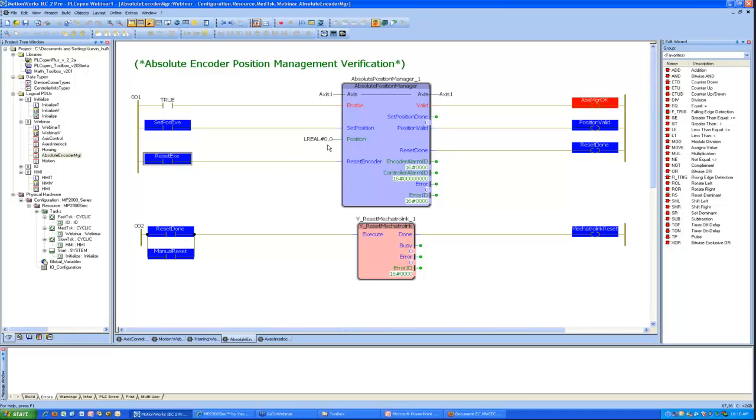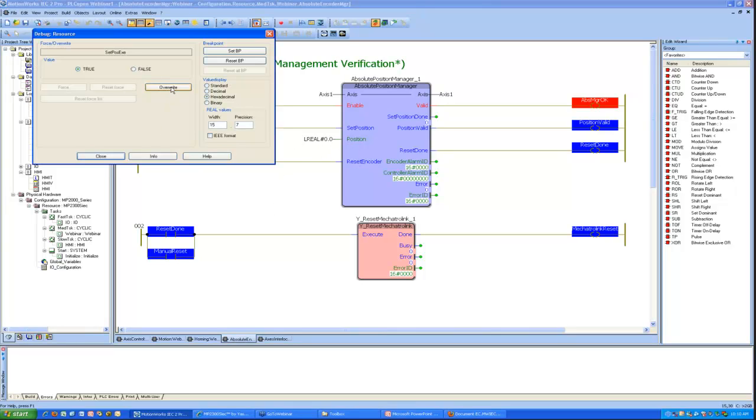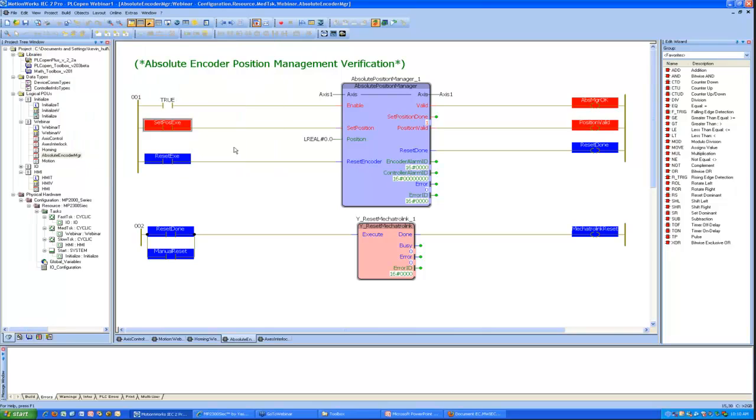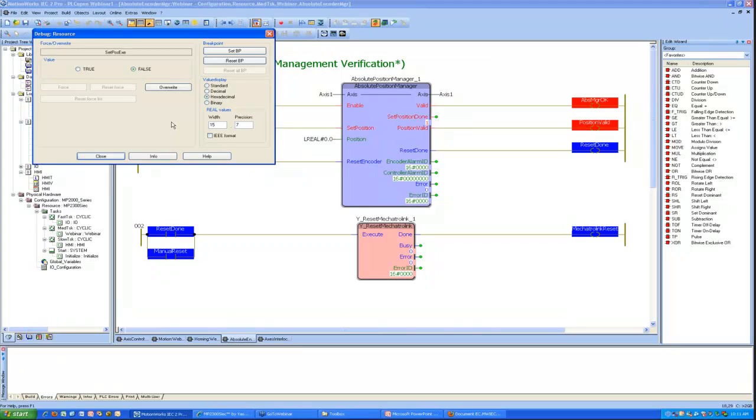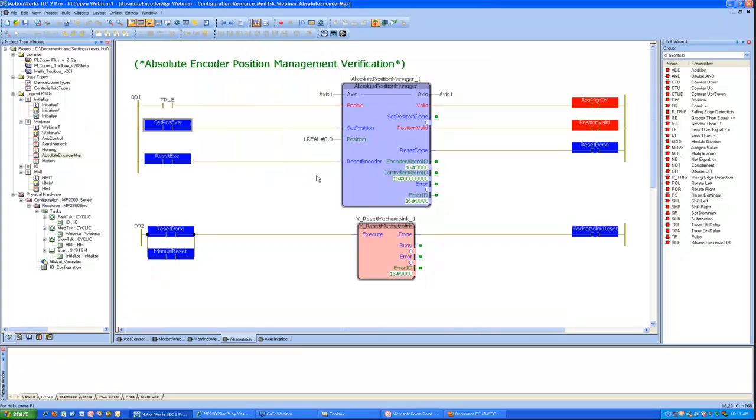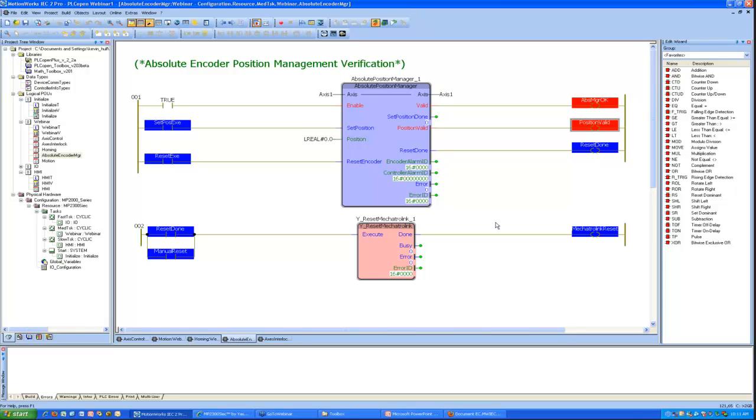And at this point, I still do not have a valid position. And that is because I need to reset the position. I need to physically move the axis and calibrate it back to a known position and define that position and set it using this function block. And at that point, I now have, once again, a valid absolute encoder position. And so now my interlocks used elsewhere in the program are happy and would allow me to do any automatic modes of operation.